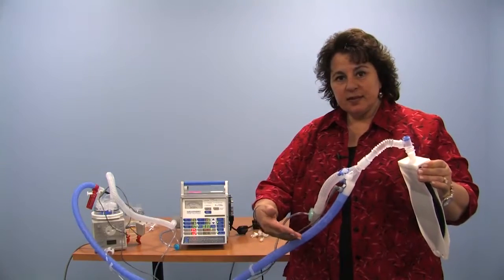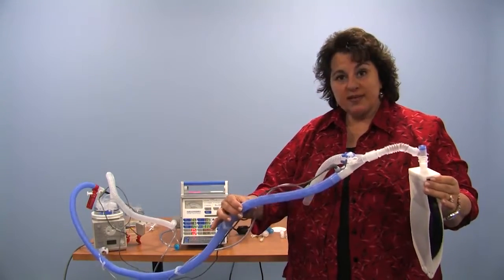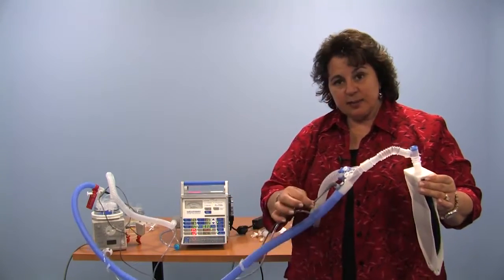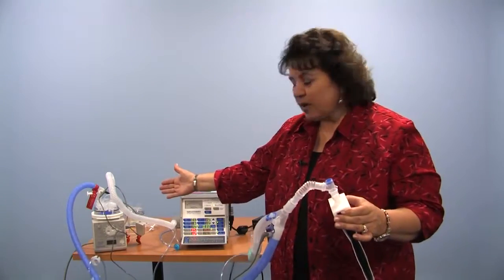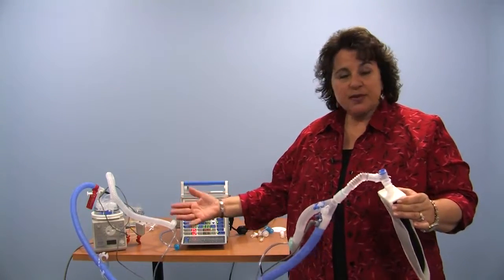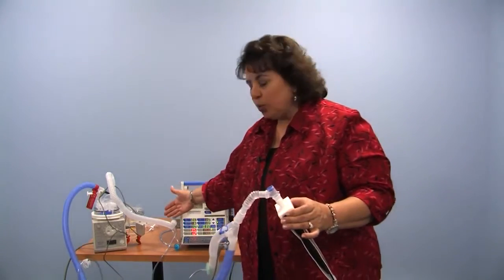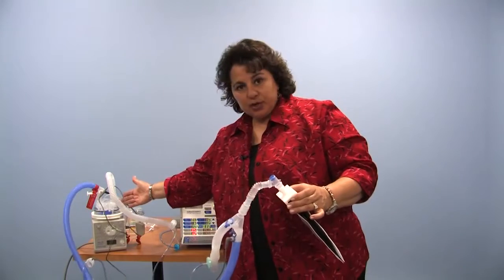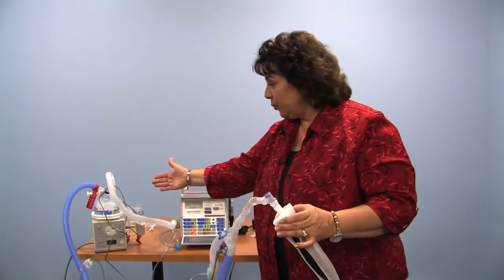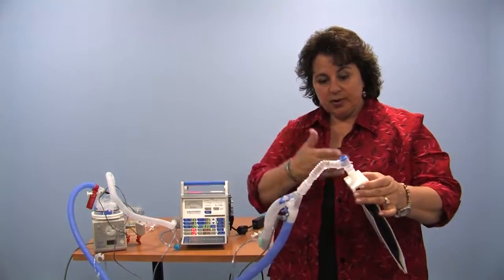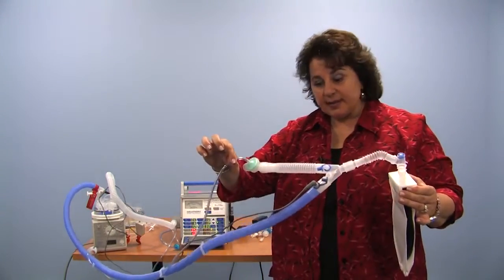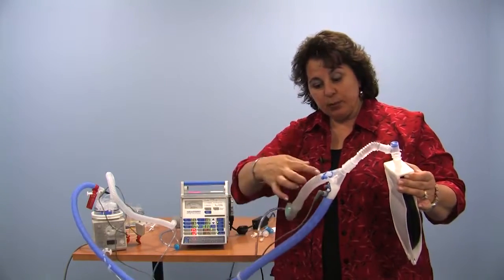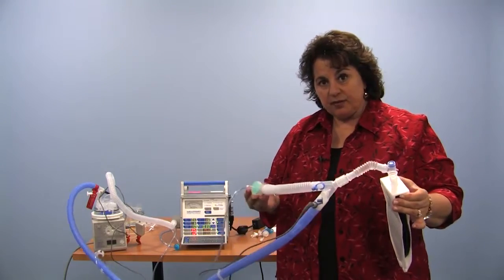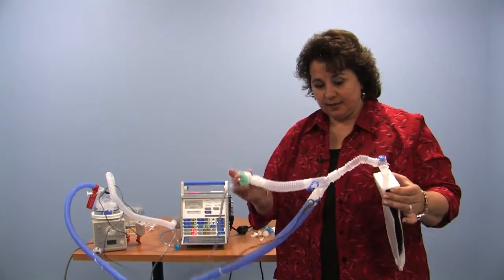Okay, now we're looking at the Newport HT50 with heated humidifier and heated tubing circuitry. So we've replaced the white dry circuit without wires for one that does have a heated wire within it. And now it is communicating with the heated humidifier. This particular one is Fisher-Paykel, but your company may provide you with a different brand. Nonetheless, the cool, dry air is coming out of the ventilator, going through the humidifier chamber, picking up heat and humidity, and coming out to your child. Then they exhale through the side that does not have heated wire in it, so there will be moisture for sure here and moisture coming out the valve. Remember not to block this. This is where your child exhales.